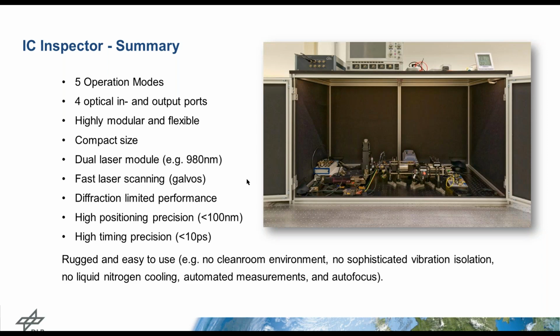And if you move the laser within the field of view of an objective, we have a positioning precision of less than 100 nanometer. And as I will show you later, for optical measurements, it's possible to have a timing precision better than 10 picosecond. The way we designed and realized our setup means we do not need a clean room environment, we do not need sophisticated vibration isolation, and no liquid nitrogen cooling is required for the CCD.